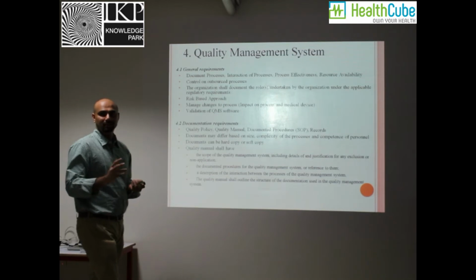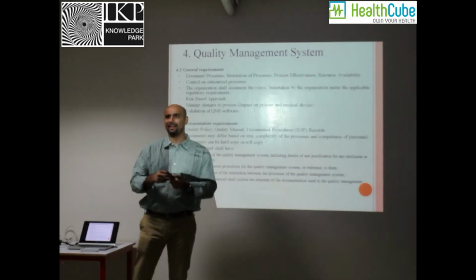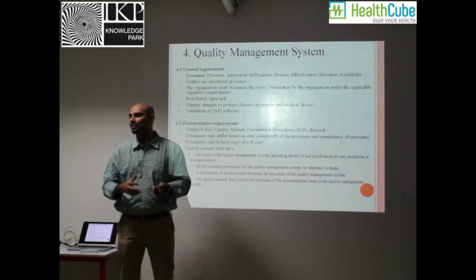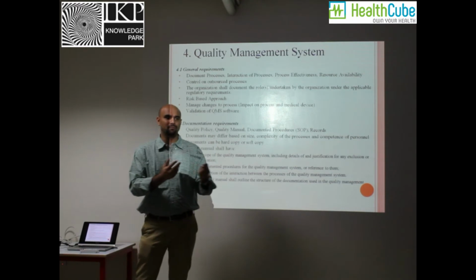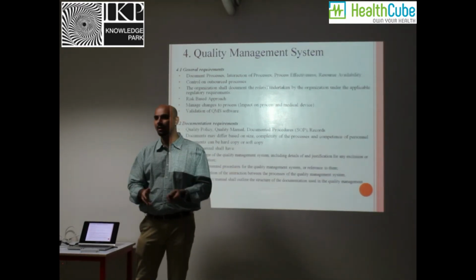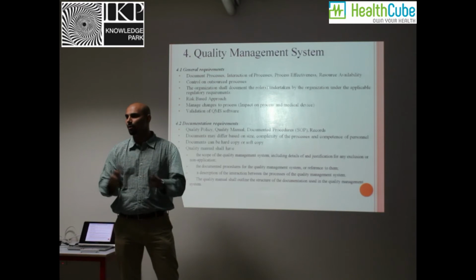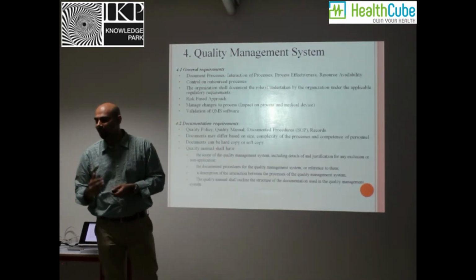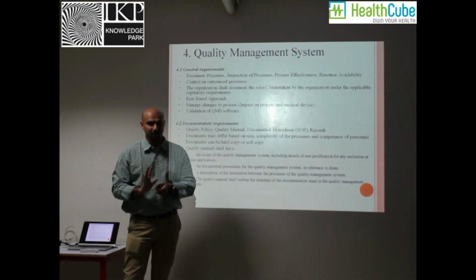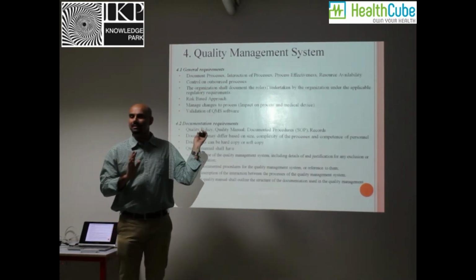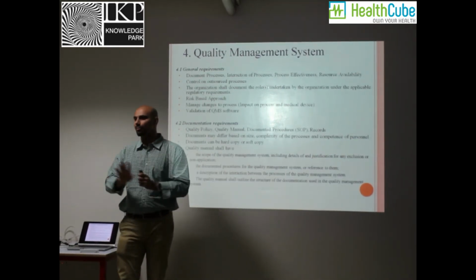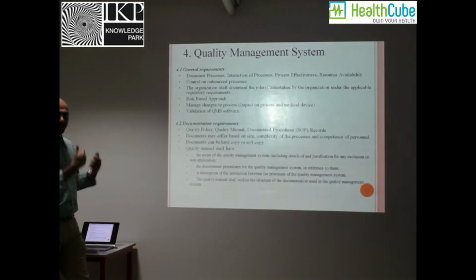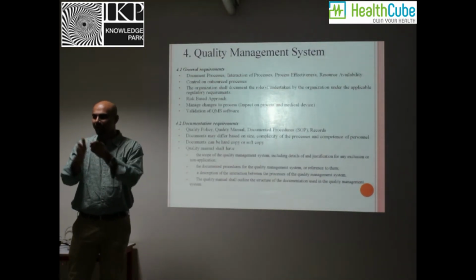Validation of QMS software, this is also something which is new. So basically, the standard leaves it up to you as to how you want to manage your documents, how you want to manage your quality management system, right? Whether you want to go through a software, whether it is a hard copy, or a mixture of hard copy and software, that's completely left up to you guys, right? But if you use software, which can be as simple as Google Drive, right? You need to validate that software. This is directly in line with a requirement from 21 CFR, that is US FDA's requirement, right? Again, this was not there in the previous version, a new edition, which puts you in line with US FDA's requirement.